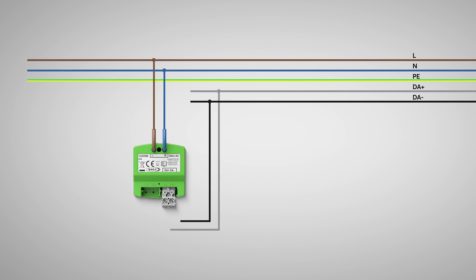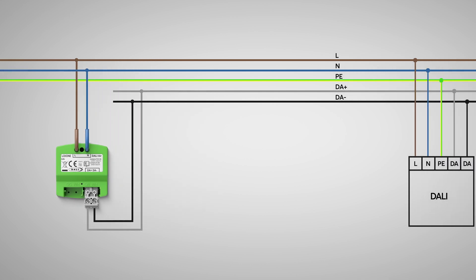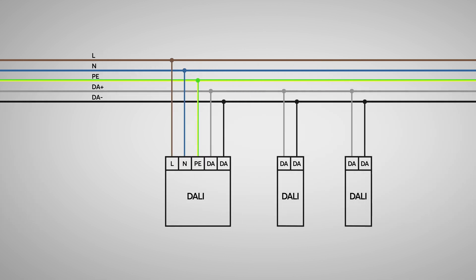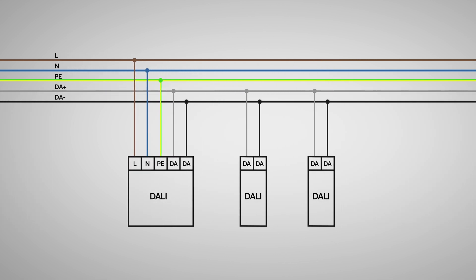This means it doesn't matter how the data lines are connected, and DALI Air has an internal power supply, which is also transmitted via the data line. An expensive DALI power supply is therefore not necessary.